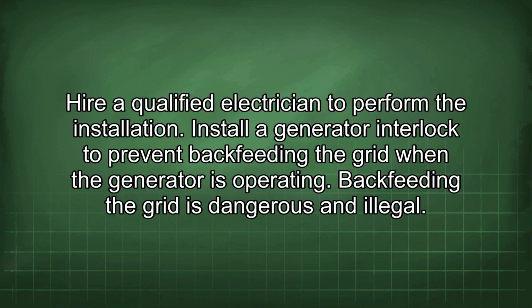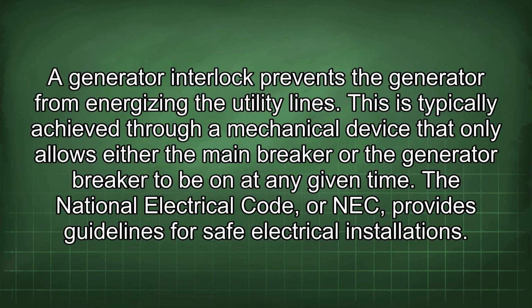Install a generator interlock to prevent backfeeding the grid when the generator is operating. Backfeeding the grid is dangerous and illegal. A generator interlock prevents the generator from energizing the utility lines. This is typically achieved through a mechanical device that only allows either the main breaker or the generator breaker to be on at any given time.